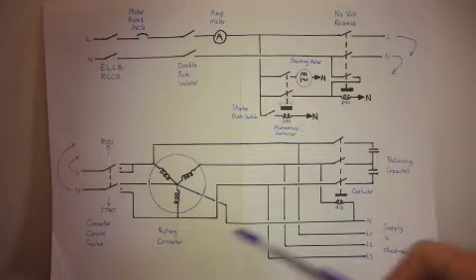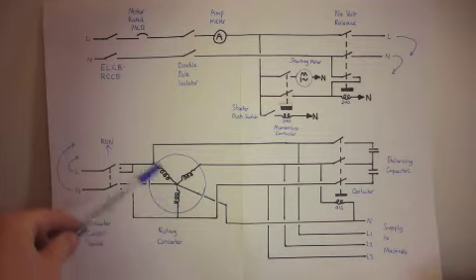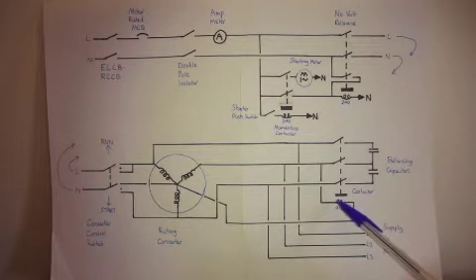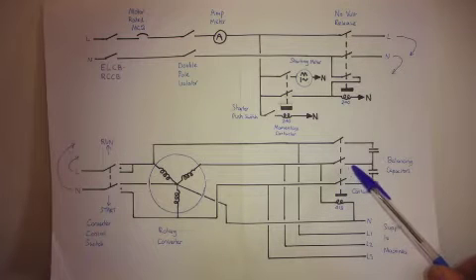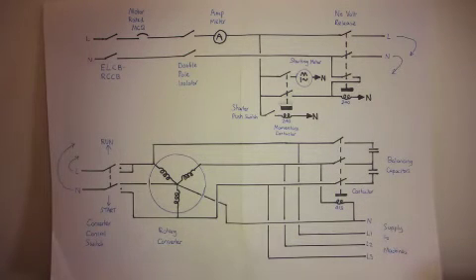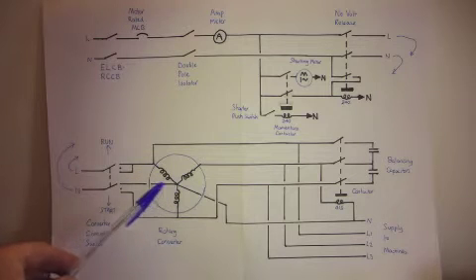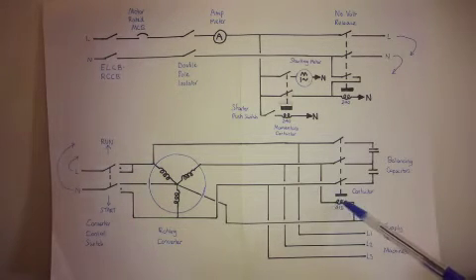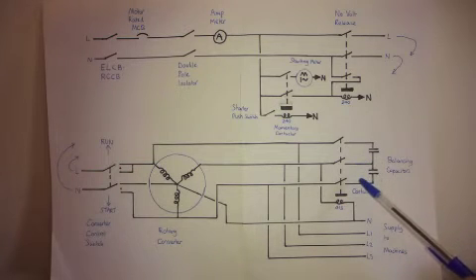But what it means is that when you start the converter by applying voltage across two phases, there is insufficient voltage to pull this coil down. What happens is it'll hum and buzz but not pull down and not make that contact. When the full voltage is applied by putting 240 across one coil and to the star point, there's then sufficient voltage for this contactor to pull in and switch the capacitors into circuit.